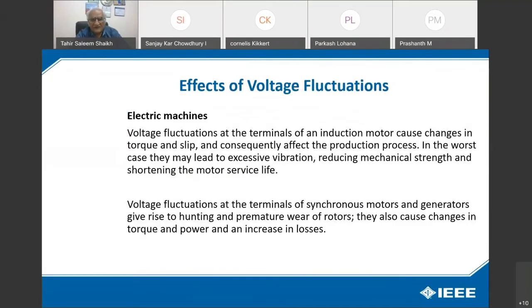Electric machines: voltage fluctuation at the terminals of an induction motor causes changes in torque. The torque will vary, and there will be a humming sound and slip, and consequently this affects the production process. In the worst case, they may lead to excessive vibration, reducing mechanical strength and shortening the motor service life. Voltage fluctuation at the terminals of synchronous motors and generators gives rise to hunting and premature wear of rotors. They also cause changes in the torque and power and an increase in losses.